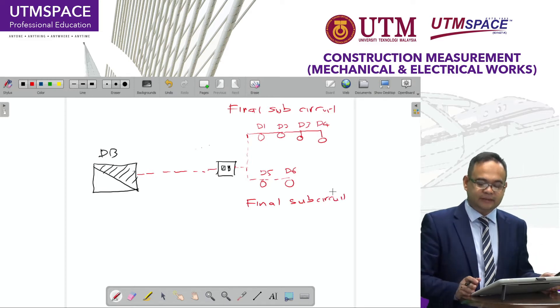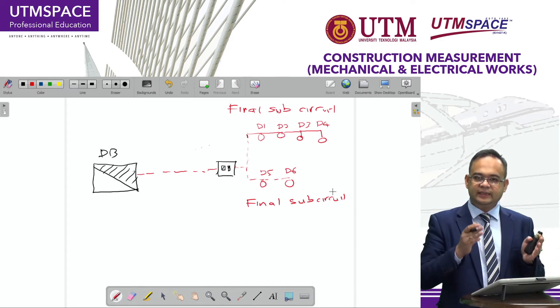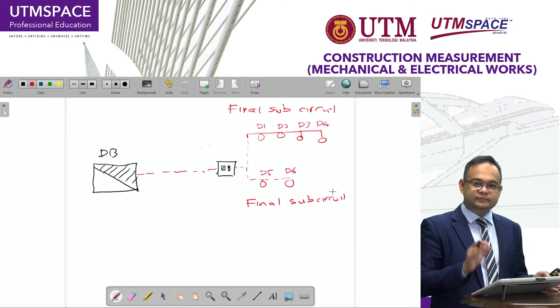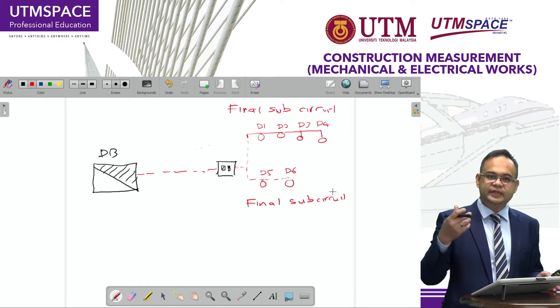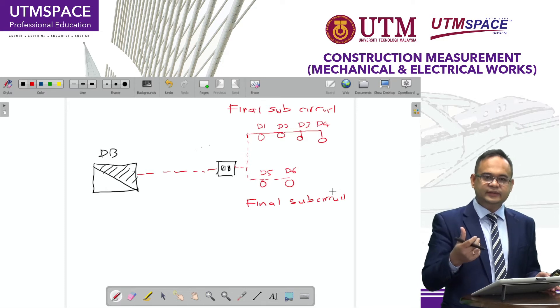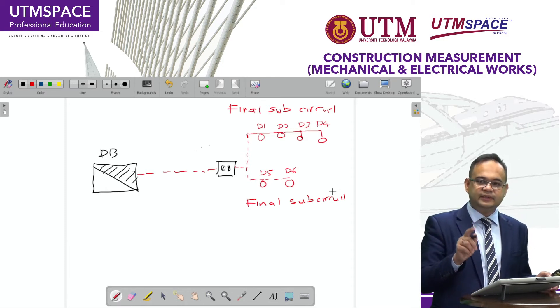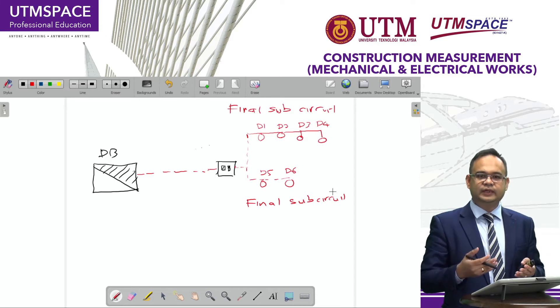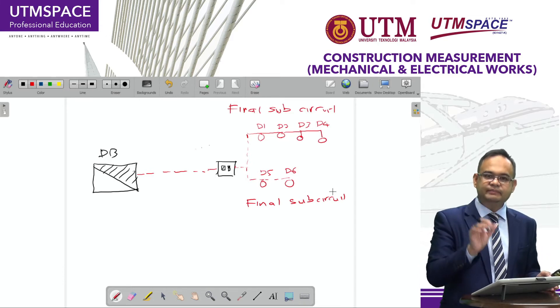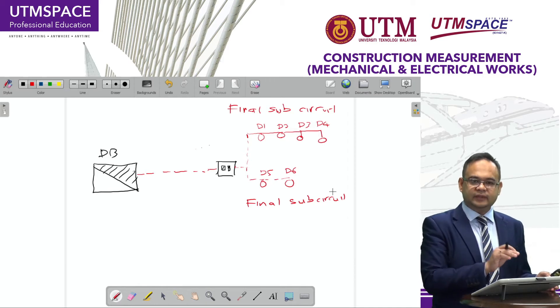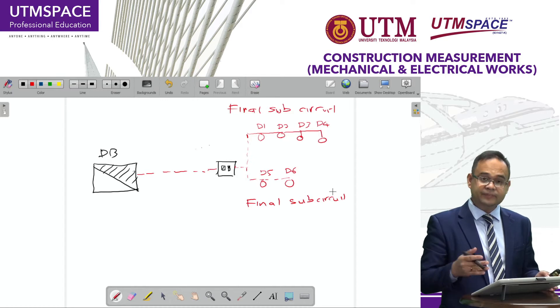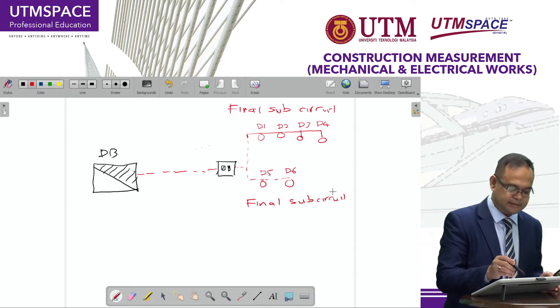This is what we call a final sub-circuit. In SMM2, from DB to switch, we measure in middle length — the cable and also the conduit in middle length, in the cable section. But for the final sub-circuit, no need to measure the cable, no need to measure the socket, no need to measure the downlight, et cetera. You just measure in number the final sub-circuit. This is the way we prepare the BQ — only mention in number, so no need to measure the length of the cable, because this is a requirement by section R16 to R18 about the final sub-circuit.